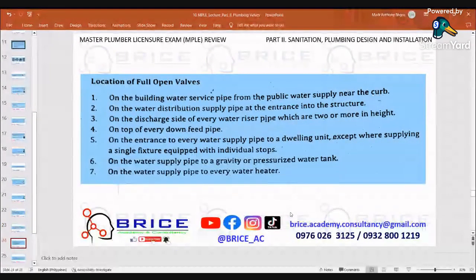Location of full open valves. Number 1, on the building water service pipe from the public water supply near the curb. Number 2, on the water distribution system supply pipe at the entrance into the structure. Number 3, on the discharge side of every water riser pipe, which are two or more stories in height. Number 4, on top of every downfeed pipe.